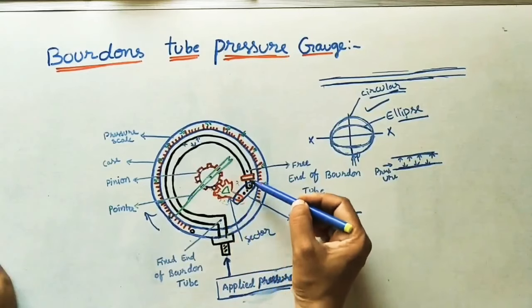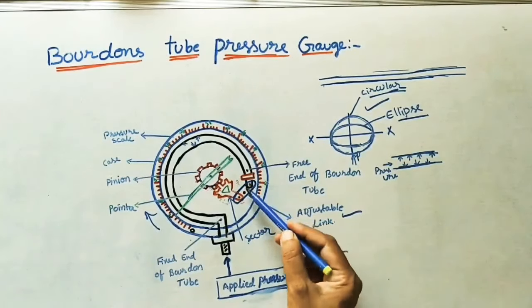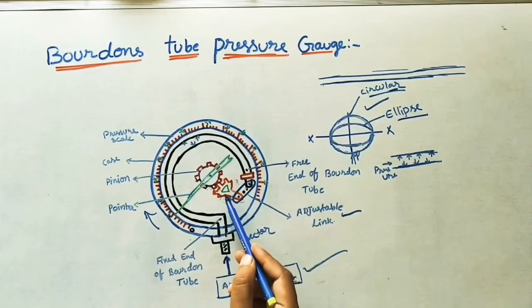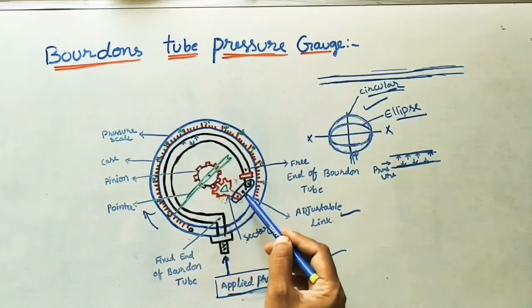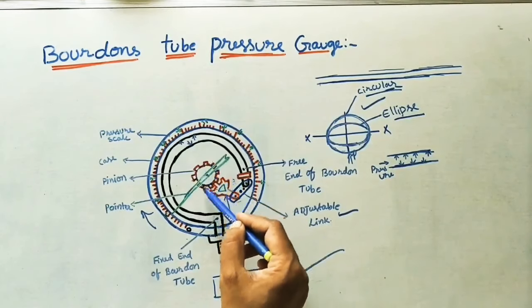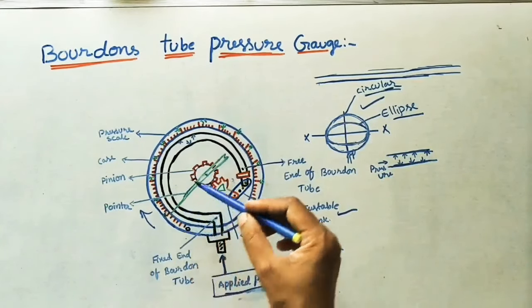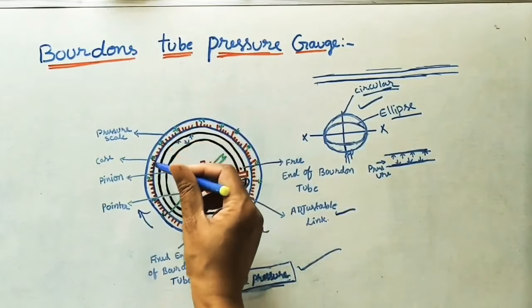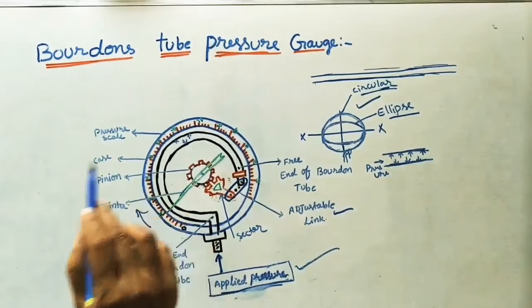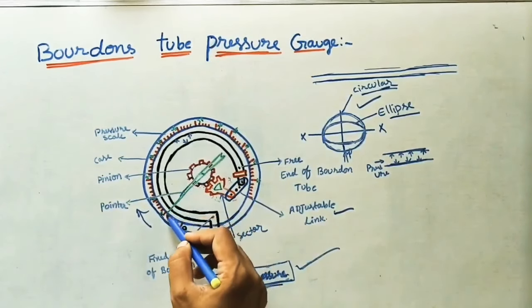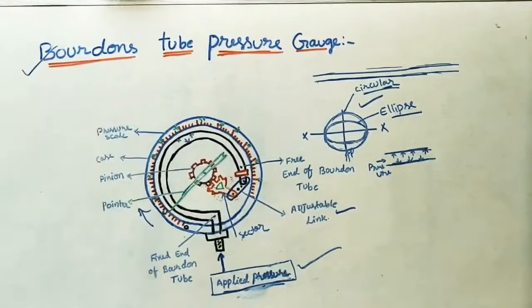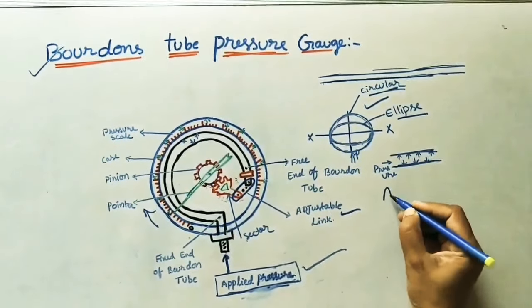Because of this deflection from elliptical to circular form, the adjustable link also deflects. This drags the adjustable link and the sector, which rotates the pinion. The pinion rotation causes the shaft to rotate, which moves the pointer over the circular scale. The pointer reading — for example 5, 10, or 15 bars — gives the value of the applied pressure. This is the complete working process of the Bourdon tube pressure gauge.